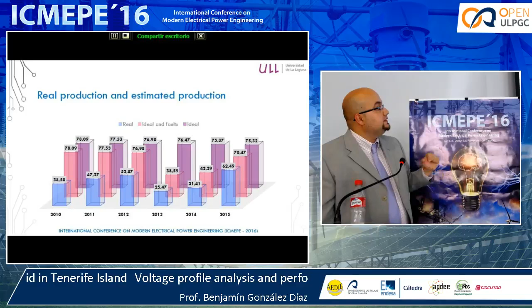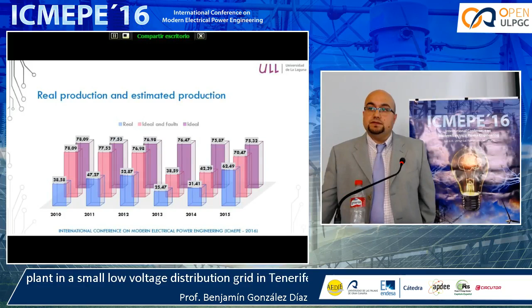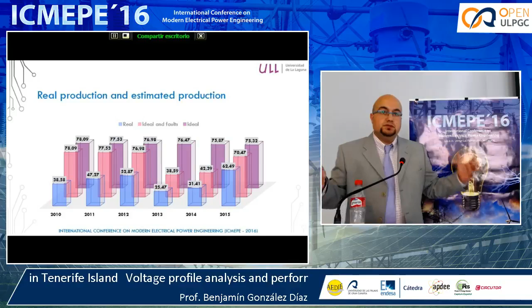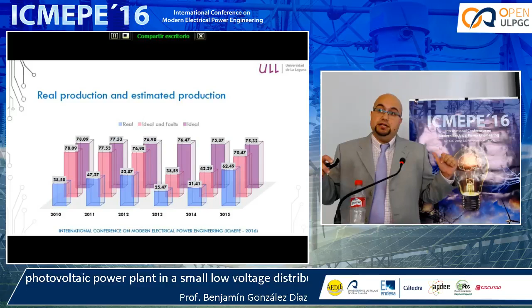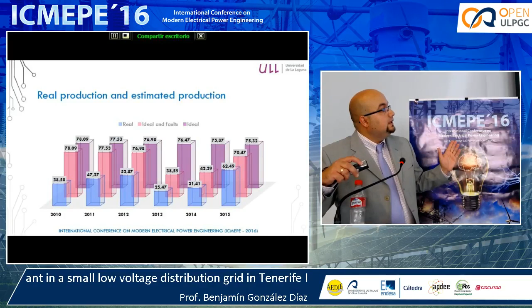So this is the real case, in blue, of the production in megawatts of the PV power plant. We can see the ideal case, but a problem was detected in one of the inverters. The electronics of the inverter were damaged by lightning during 2013 and 2014. For this reason, in that case, the production is lower. The ideal case we can calculate with the resource, with the meteorological data, and so on. We can compare the ideal and the fault. There is a huge problem inside. And after the lightning, the power electronics were replaced in one of the inverters, the 25 kilowatt inverter. And there was an improvement, not total, but an improvement in comparison with the other case.